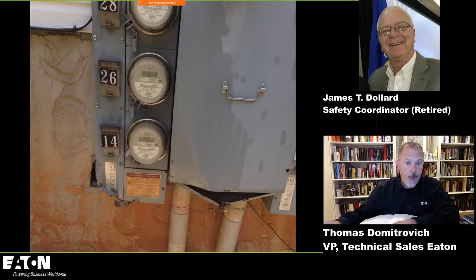This is abnormal. Yeah. And normal versus abnormal really only comes in where we take a look at opening or closing a switch, opening or closing a circuit breaker, and when we take a look at likelihood. So what we do in Table 130.5(C) is take the provisions in 130.2(A)(4) and run them down the road of likelihood. And we tell you if it's in abnormal condition or not properly maintained, then there is a likelihood.